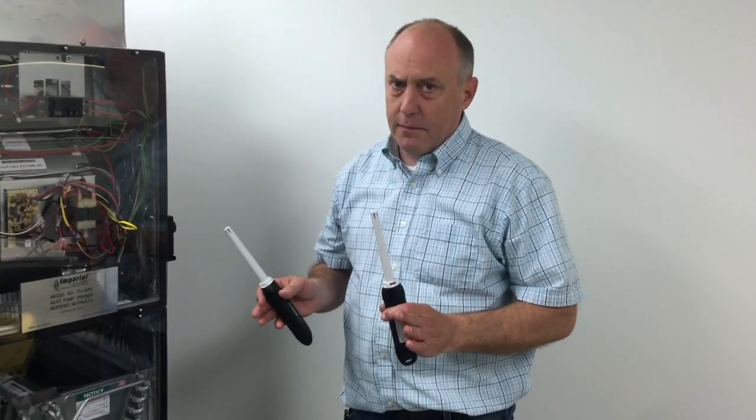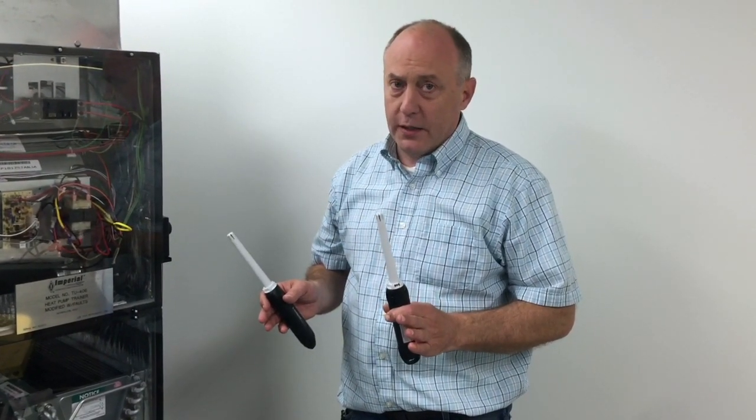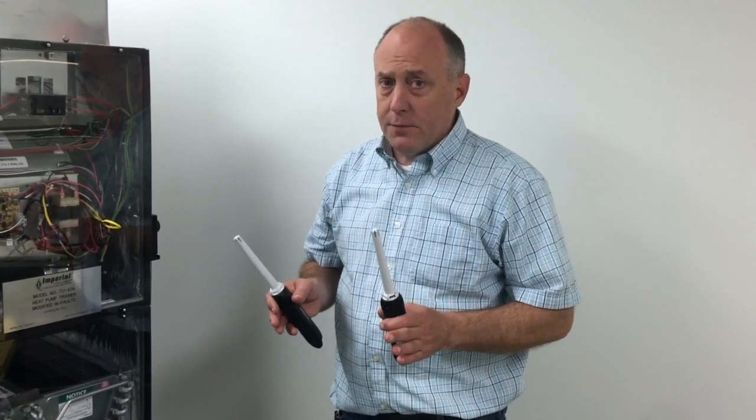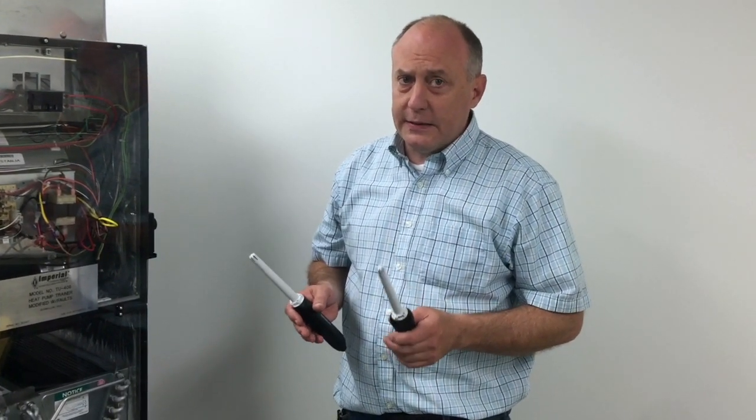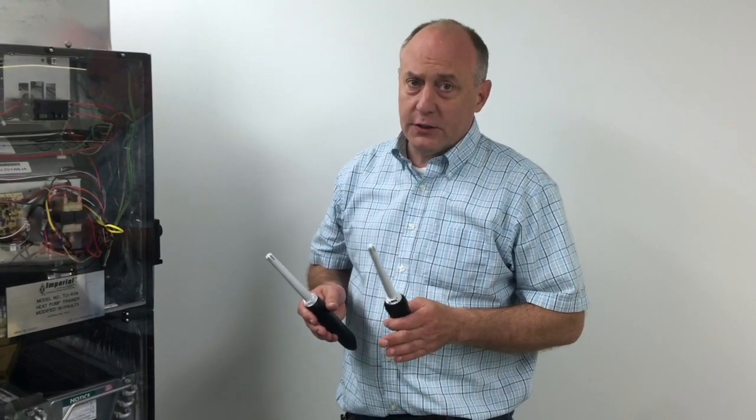A couple of things we want to make sure that you understand when putting the probes in place in the ductwork. You can't stress this enough if you're going to get good readings. If you don't put the probes in the right location, you're going to constantly get what looks like low air flow readings when in fact the air flow is just fine.